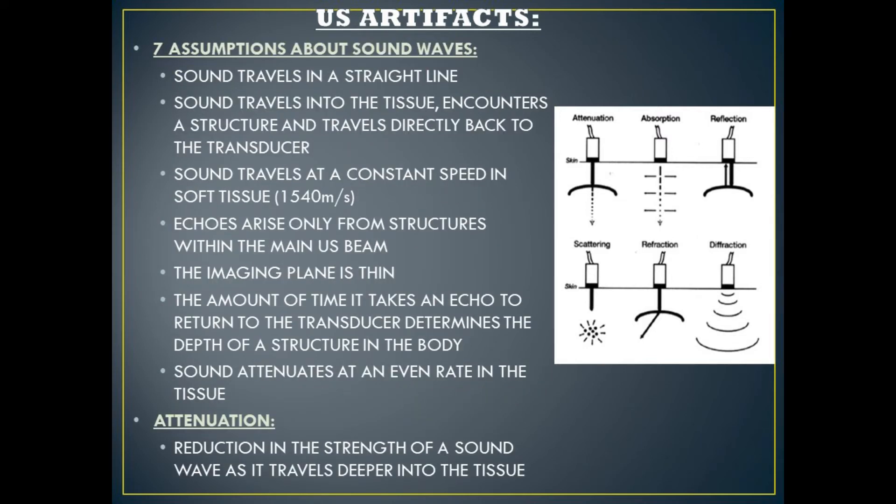Ultrasound artifacts occur because one of the seven assumptions that ultrasound machines make about sound waves fails to occur. Assumption one is that sound travels in a straight line. Assumption two, sound travels into the tissue, encounters a structure, and travels directly back to the transducer. Assumption three, sound travels at a constant speed in soft tissue, which is 1540 meters per second.